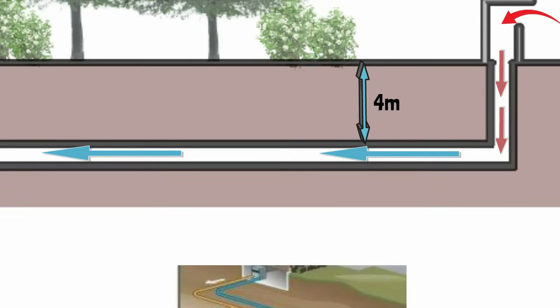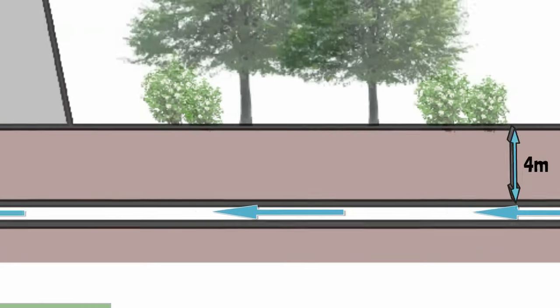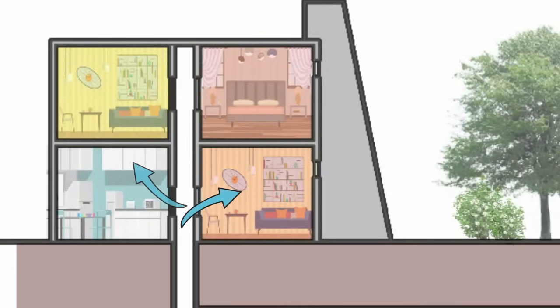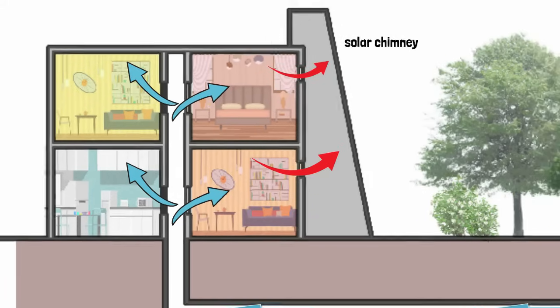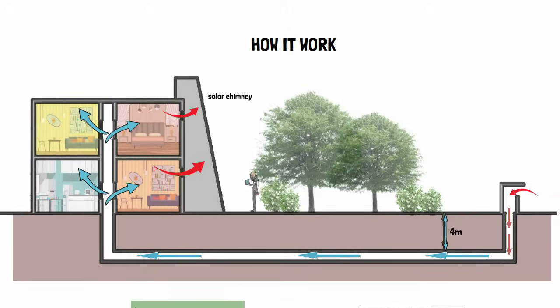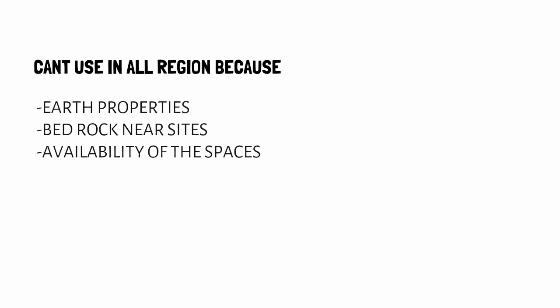The pipe size varies from 3 inch to 30 inch. A smaller diameter pipe requires more energy to move air due to friction in the pipe. After the air is treated, it goes inside the building. A solar chimney can also be added to extract hot air from the room. However, Earth Air Tunnel systems may not be suitable in all regions due to earth properties, bedrock near the project site, and availability of space.